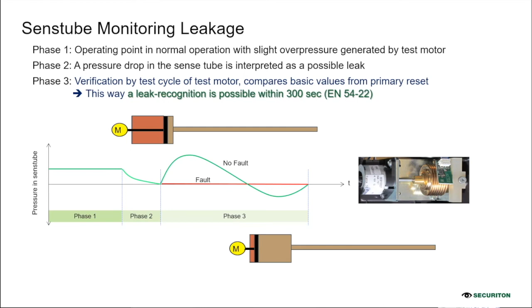In picture 1, phase 1 is the operating point in normal operation, with slight overpressure generated by the test motor. Picture 2, phase 2: a pressure drop in the sensing tube is interpreted as a possible leak. Picture 3, phase 3: verification by the test cycle of the test motor. There is always a test cycle, and it compares the basic value from the primary reset, which you did at the start of the product.